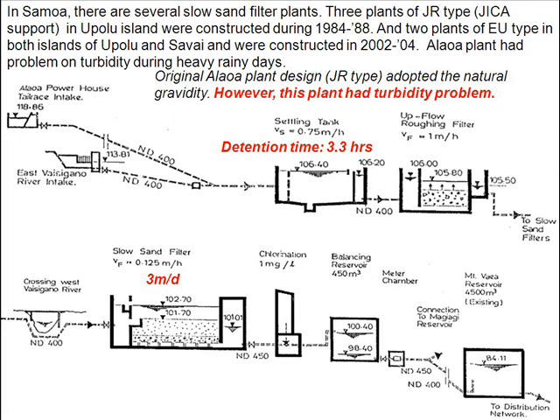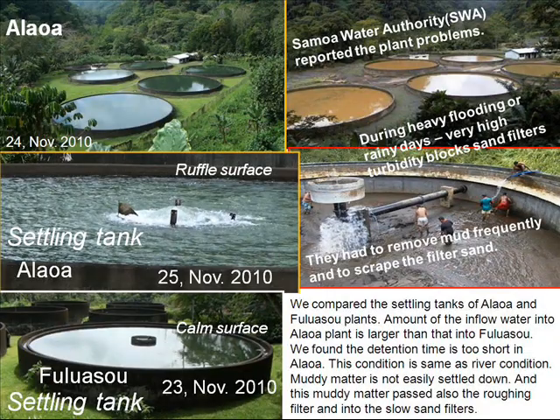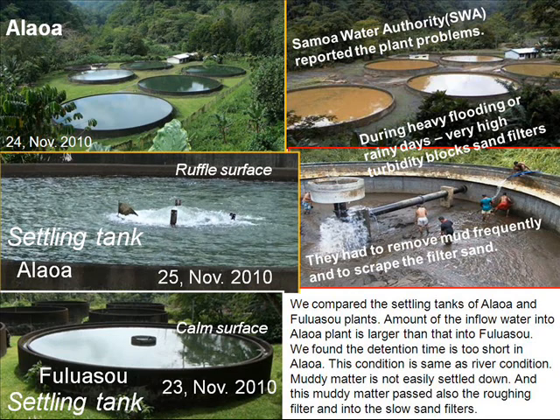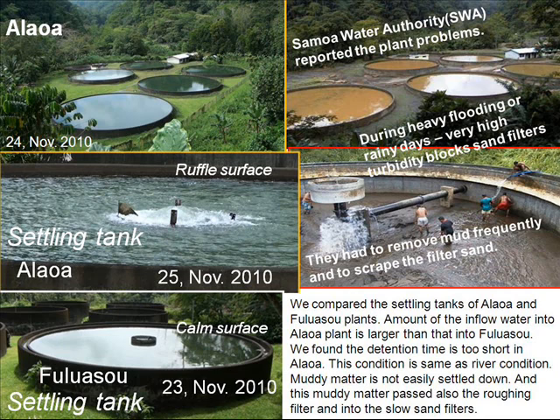The original detention time of the settling tank was 3.3 hours. The amount of inflow water into Alaoa plant is larger than into Fuluasou plant. We found the detention time is too short in Alaoa. This condition is the same as a river condition — muddy matter does not easily settle down, and this muddy matter passed through the roughing filter and into the slow sand filters.